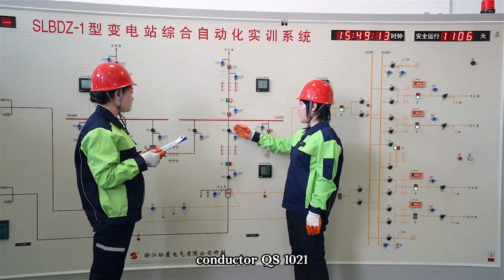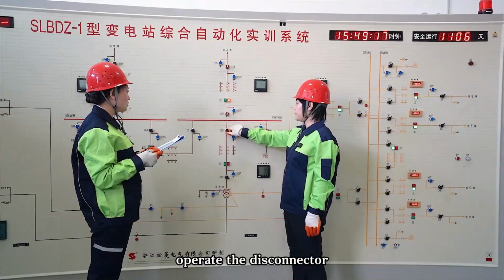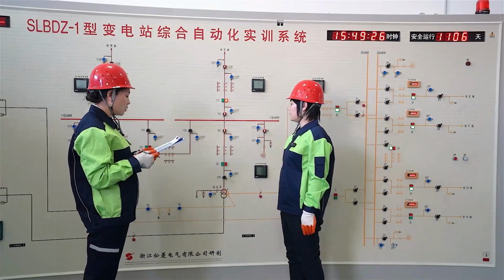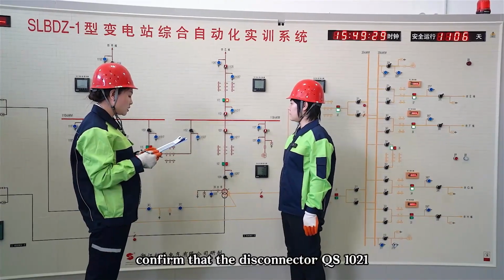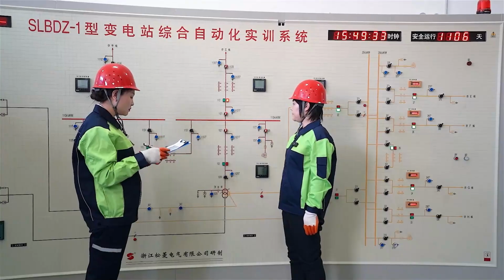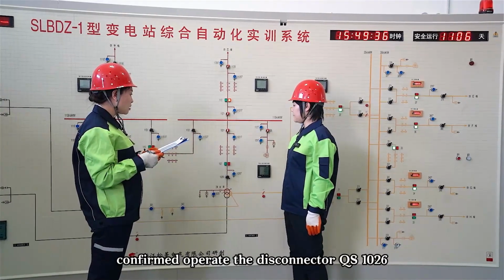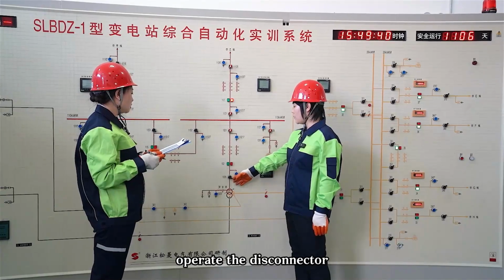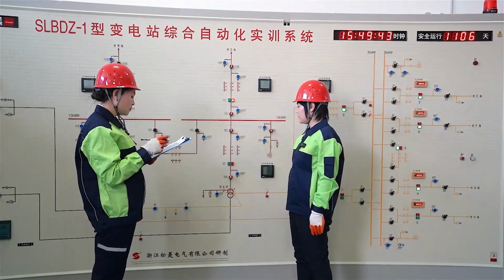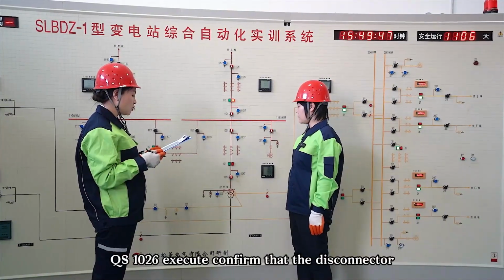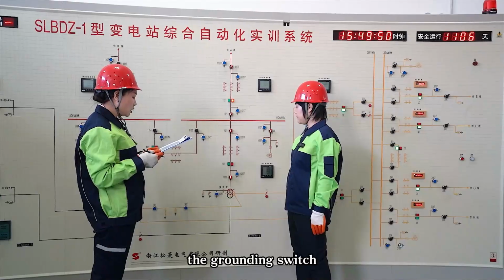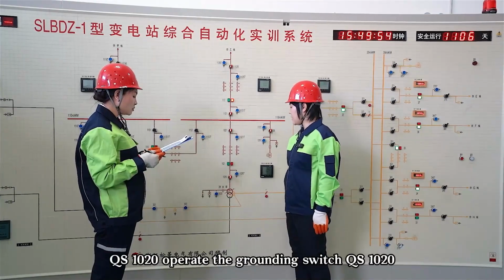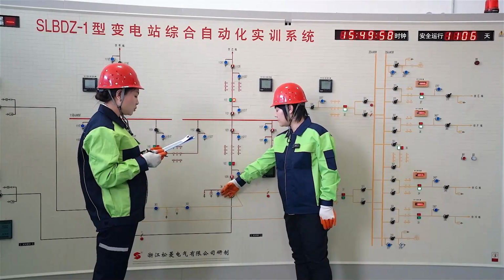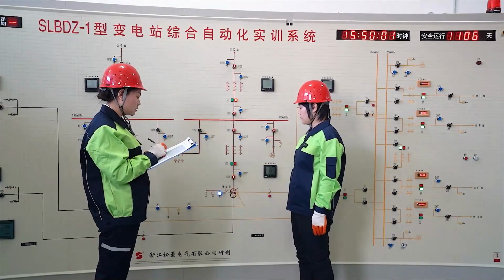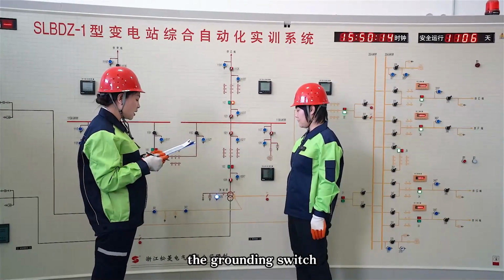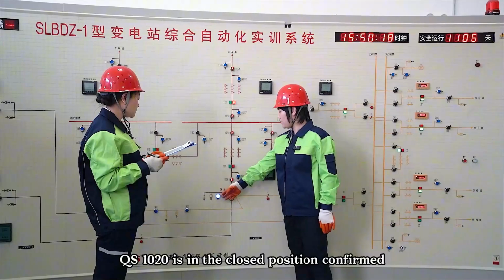Confirmed. Operate the disconnector QS 1021. Execute. Confirm that the disconnector QS 1021 is in the closed position. Confirmed. Operate the disconnector QS 1026. Execute. Confirm that the disconnector is in the closed position. Operate the grounding switch QS 1020. Execute. Confirm that the grounding switch QS 1020 is in the closed position. Confirmed.